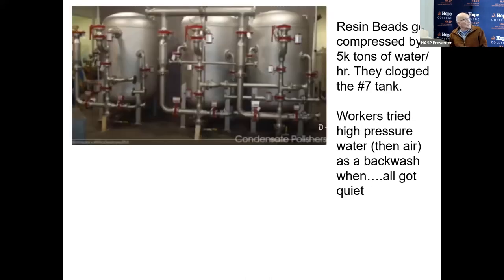That's not key. Here's three of the polishers, three of the eight polishers. Resin beads, little plastic beads. I meant to bring some, but trust me, plastic beads look like rice. They look like rice. They're compressed by 5,000 tons of water moving through. And they clogged in the number 7 tank. The workers tried some high pressure water, then some high pressure air as a backwash.